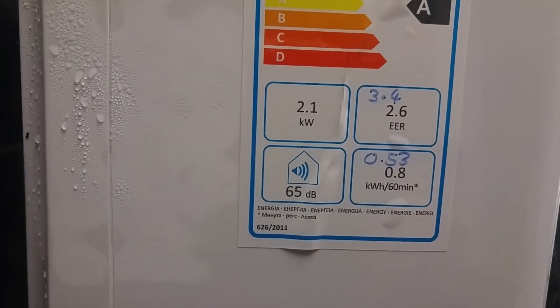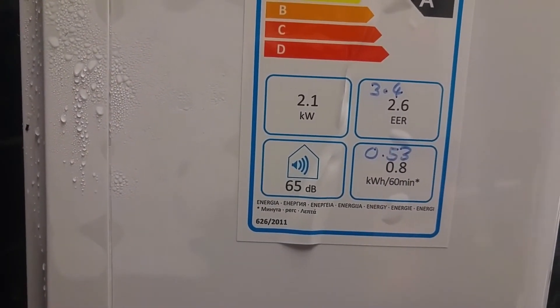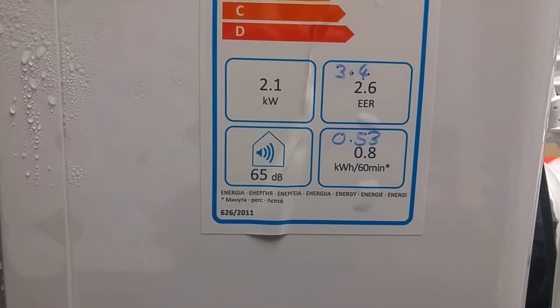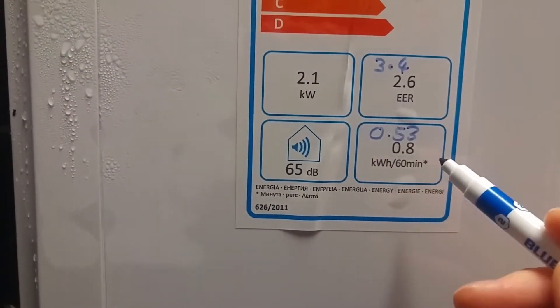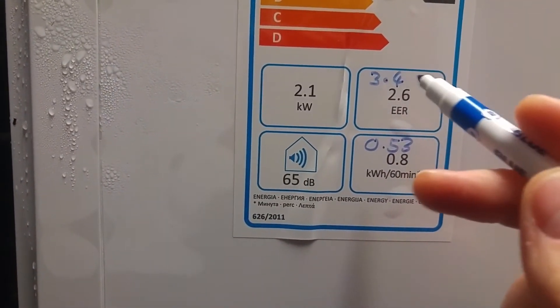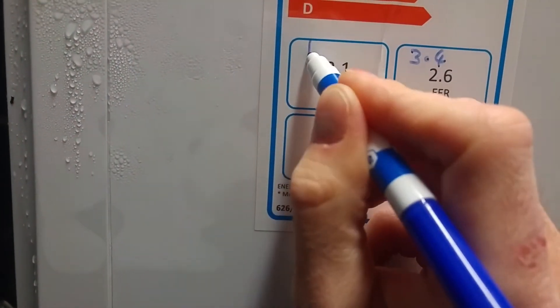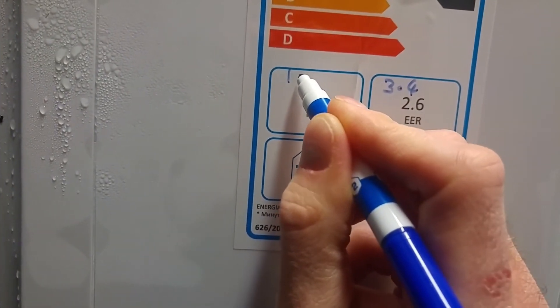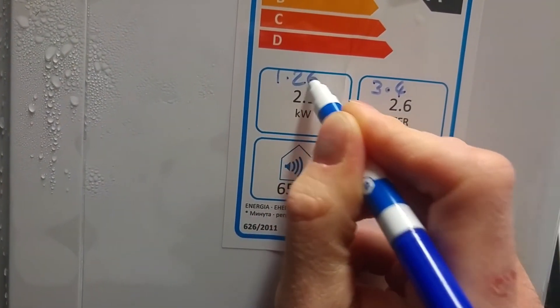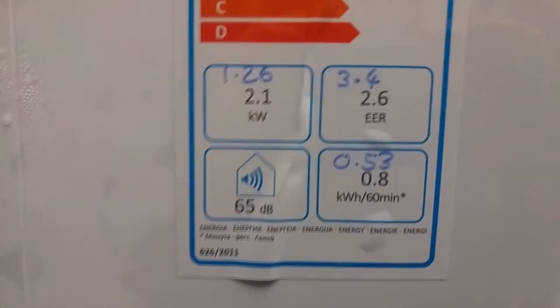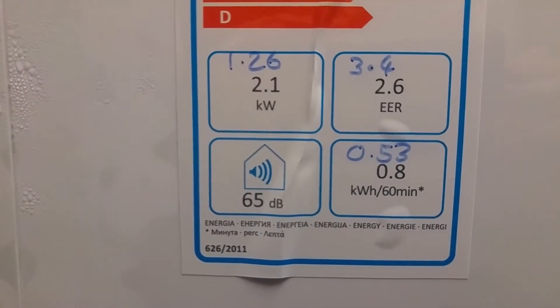But they haven't included the defrost cycle. Because 70% of the time the unit is working, but 30% of the time it's defrosting. So if you multiply that by 0.7, that times that times 0.7 gives you 1.26 kilowatts. So that's just over half of what they say.